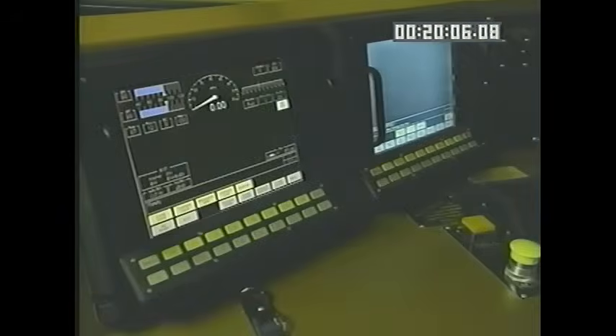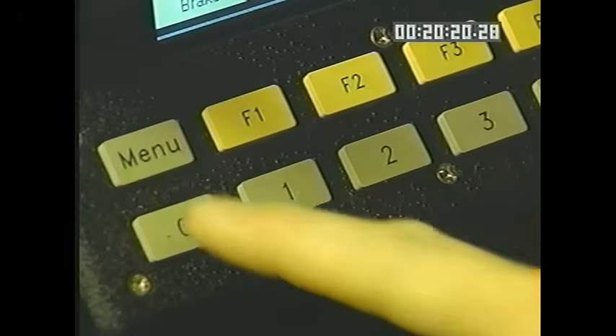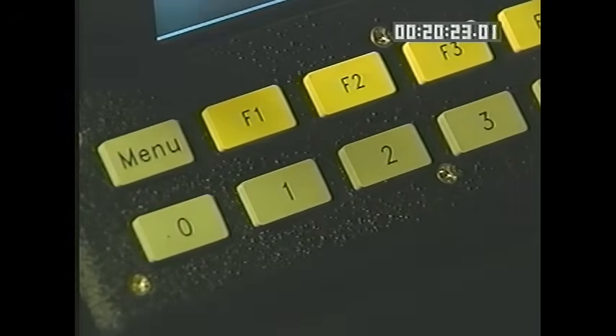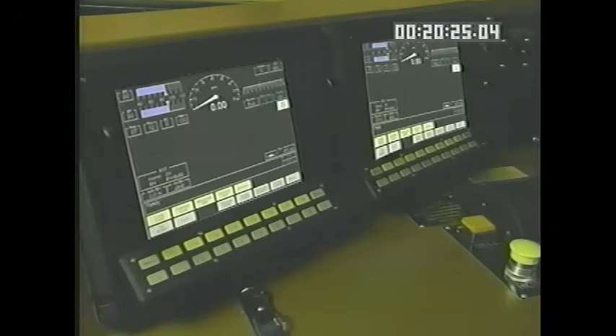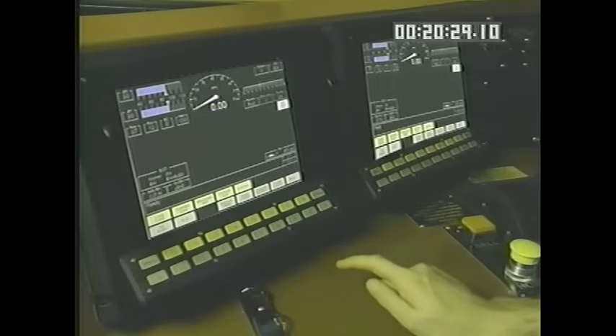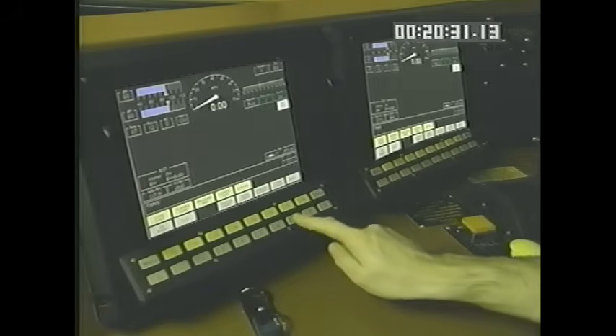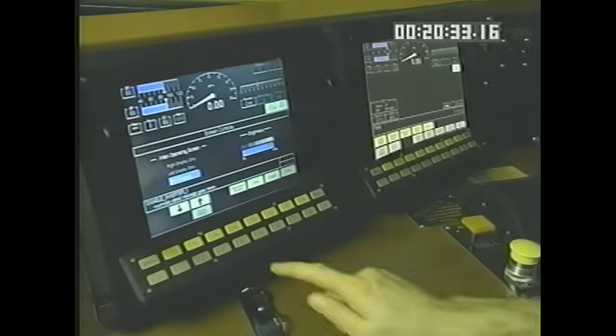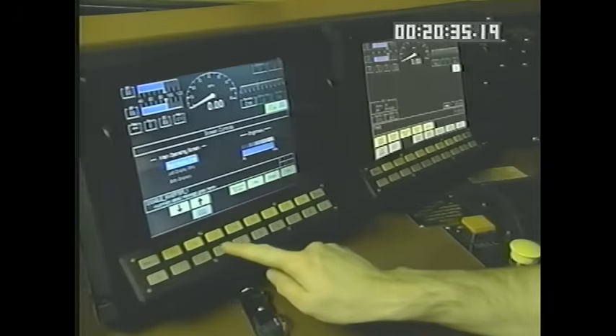In the rare instance of a screen malfunction, it's the operator's responsibility to switch the remaining display to the operating display. Pressing any display's menu key twice always causes the gauges to appear. This arrangement allows the engineer to have the additional screen displaying support information as an MMI display, while also allowing that screen to be a true backup to the operating display in the event of a problem.